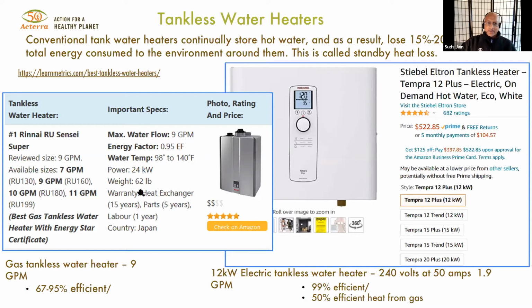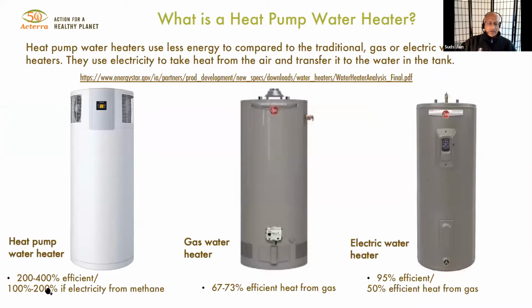So gas is an option for tankless, but electric tankless units aren't sold very often because you might need a service panel upgrade, and you don't get enough heat for multiple uses in the house. These are only 95% efficient at best, whereas a heat pump water heater can be 100 to 200% efficient when you count the methane, or 200 to 400% efficient otherwise.